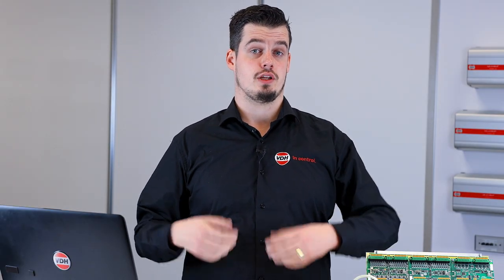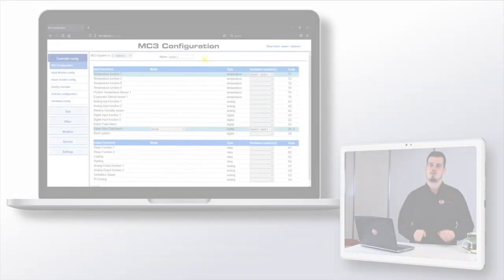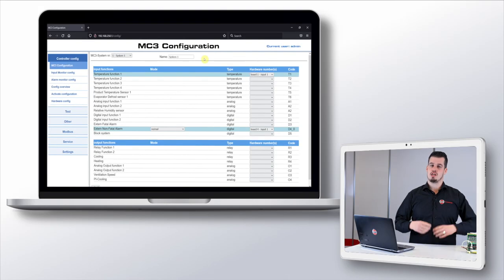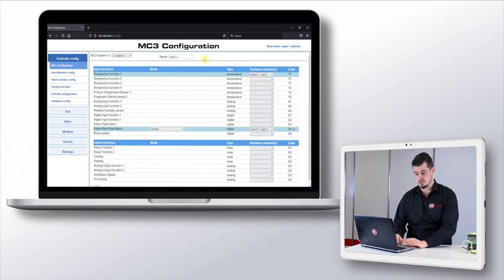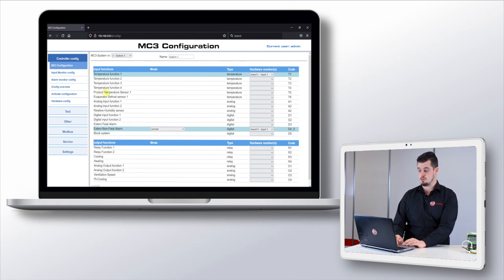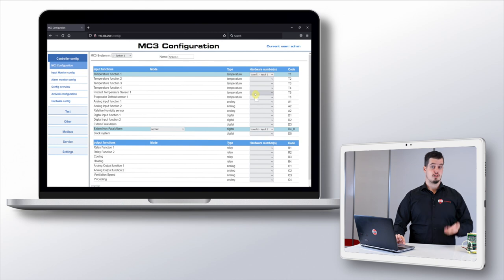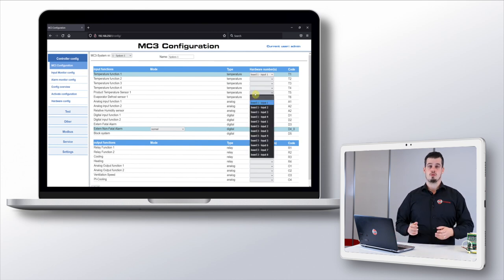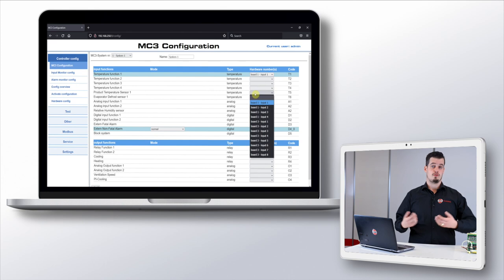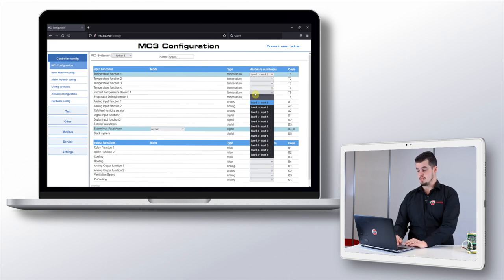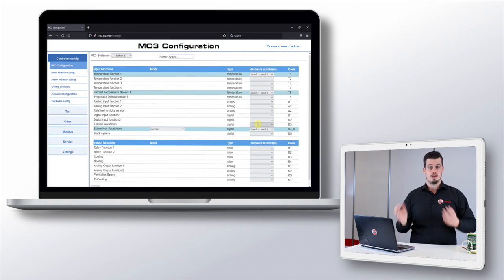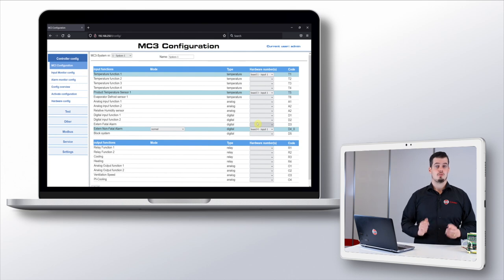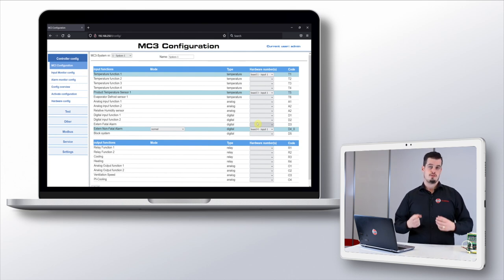Let's start with an example. We have a temperature sensor connected to board 3 input 1 and according to our schematic we want to use this as a product control sensor. First on the web page we navigate to the correct function, product temperature sensor 1, and then by pressing the dropdown menu behind the function we can see all the inputs available within our system. We then select board 3 input 1 and now we made a link between our temperature sensor in the field and the product control sensor function within the MC3.